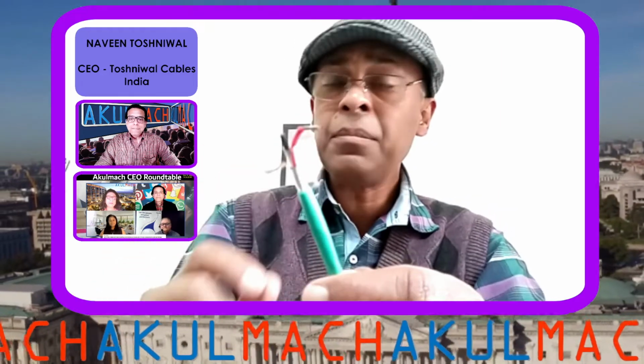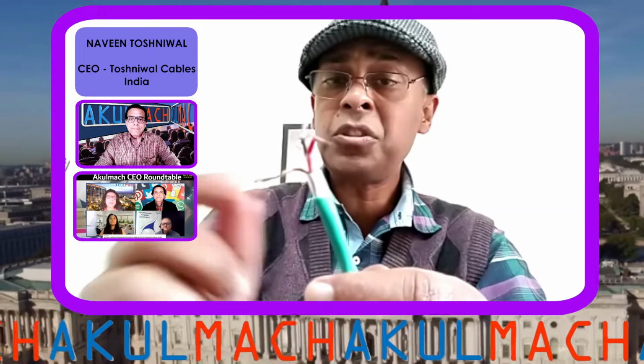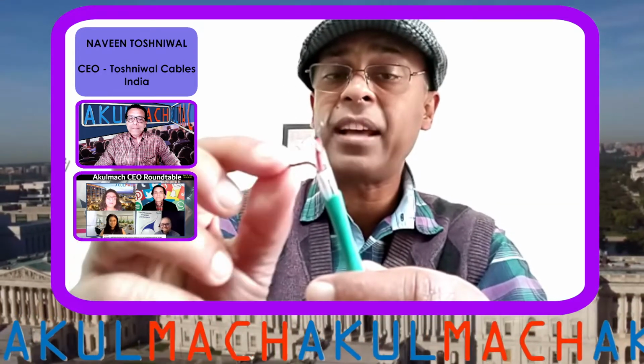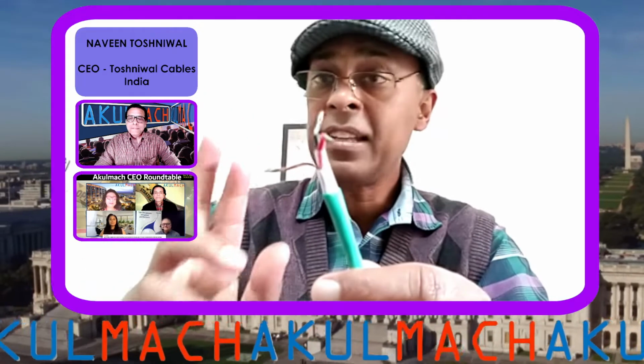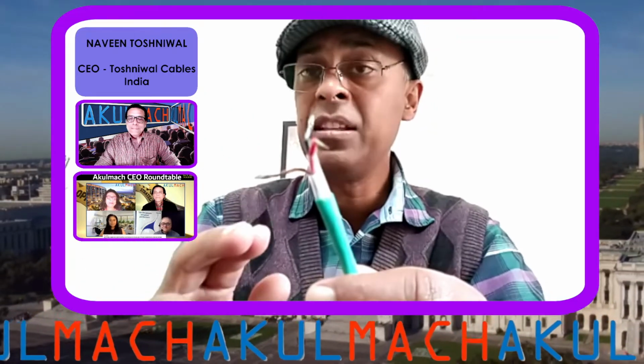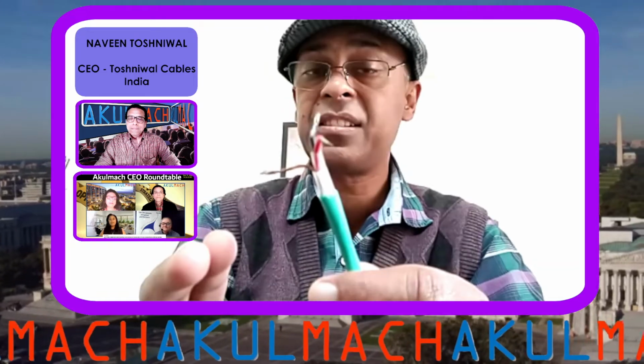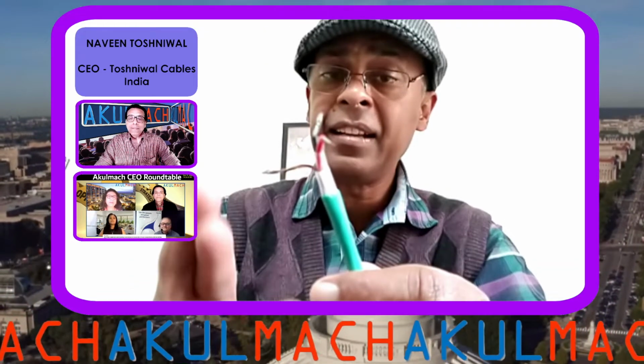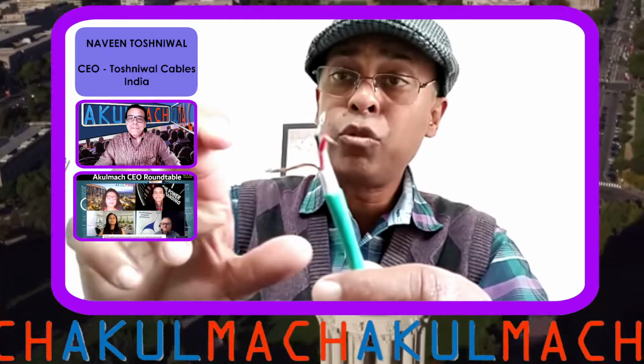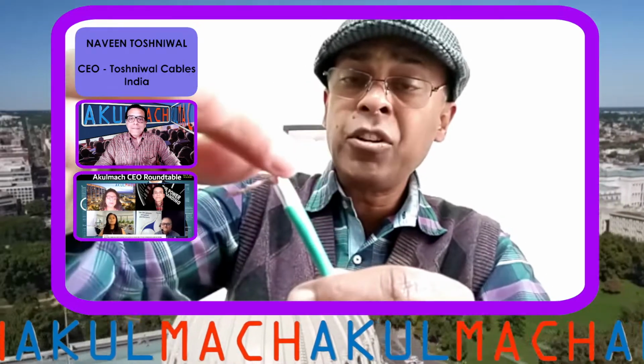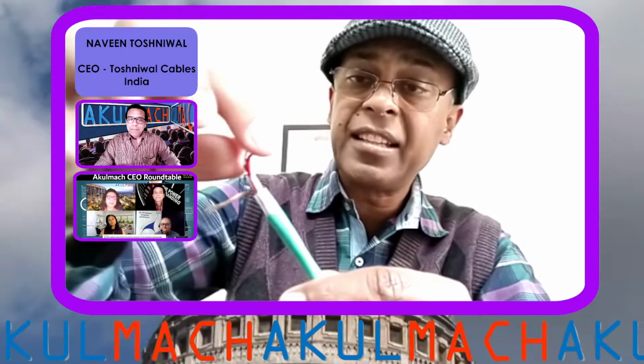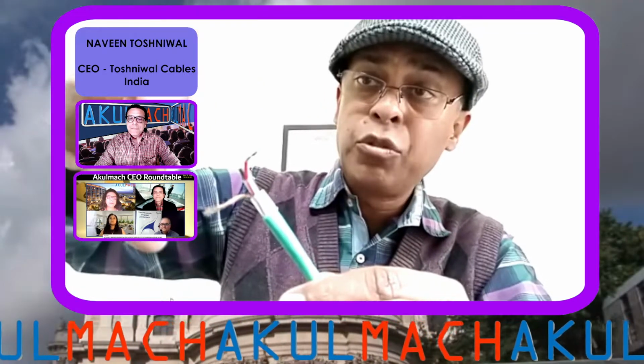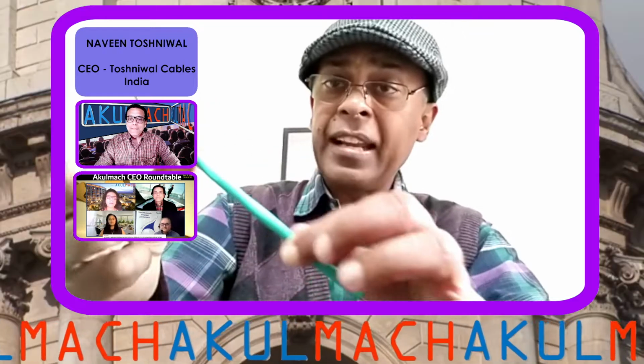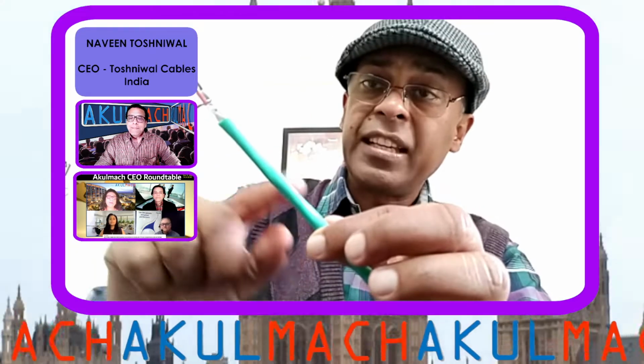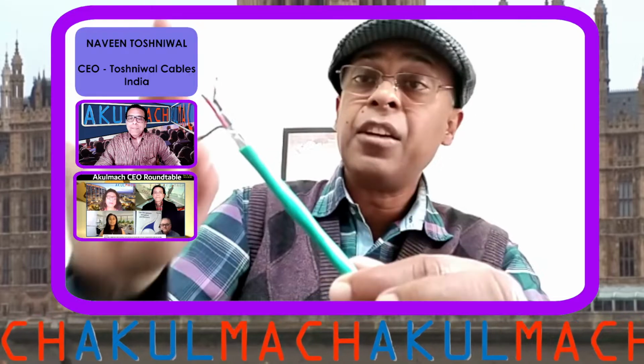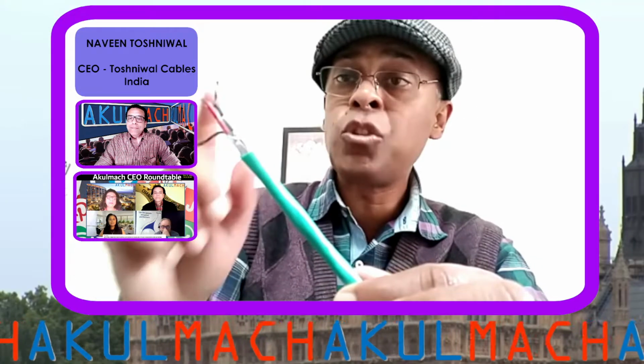Another point I want to point out is that electrostatic interference is taken care of by this shielding. There is another sort of interference in cables, which is called electromagnetic interference. Electromagnetic interference is reduced by twisting the cores like this. These two cores which you see inside the cable are actually twisted inside. If we cut open the entire cable, you will be able to see that the twisting is there inside. This twisting helps to prevent electromagnetic interference.